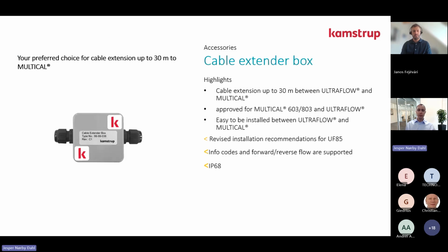We have our cable extender box. Here it makes it possible to have 30 meters between ULTRAFLOW 85 and the Multical, so the calculator. The cable extender box has also had a small revision change, so now it's IP68 as well, same as the flow sensor. The cable extender box supports the bidirectional and also all the info codes.